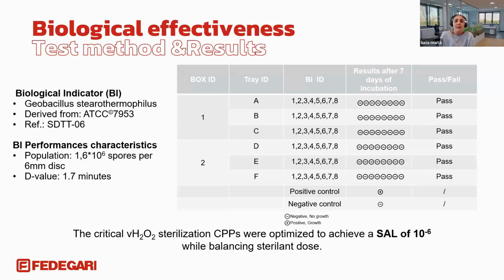Biological effectiveness was evaluated using a standard biological indicator for hydrogen peroxide, and as reported in the table, no growth was observed after incubation across all the tested locations. These results indicate that the process conditions, so the critical process parameters, are effective in achieving the required sterility assurance level.